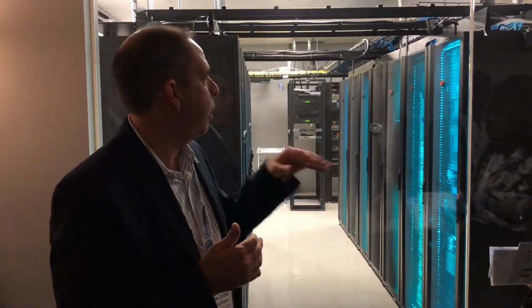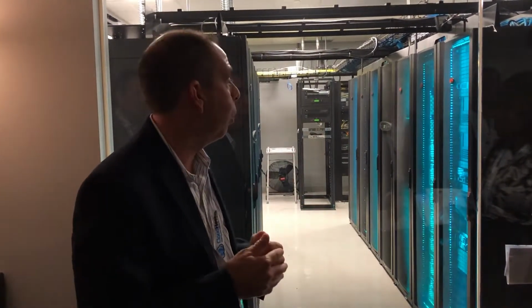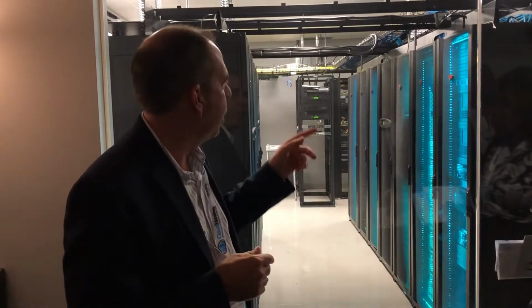Independent of that is our own bandwidth, which right now is 1G. We just signed a deal with Crown Castle, upgrading that to 10G for our network. In case you're not familiar with how the hot aisle containment works, in these two, we call them pods, the cooling units are actually in row. So those cooling units are blowing cold air to the outside of the pods and sucking the hot air from the inside. So behind those closed doors inside the pod, the temperature is about 15 degrees warmer than outside.